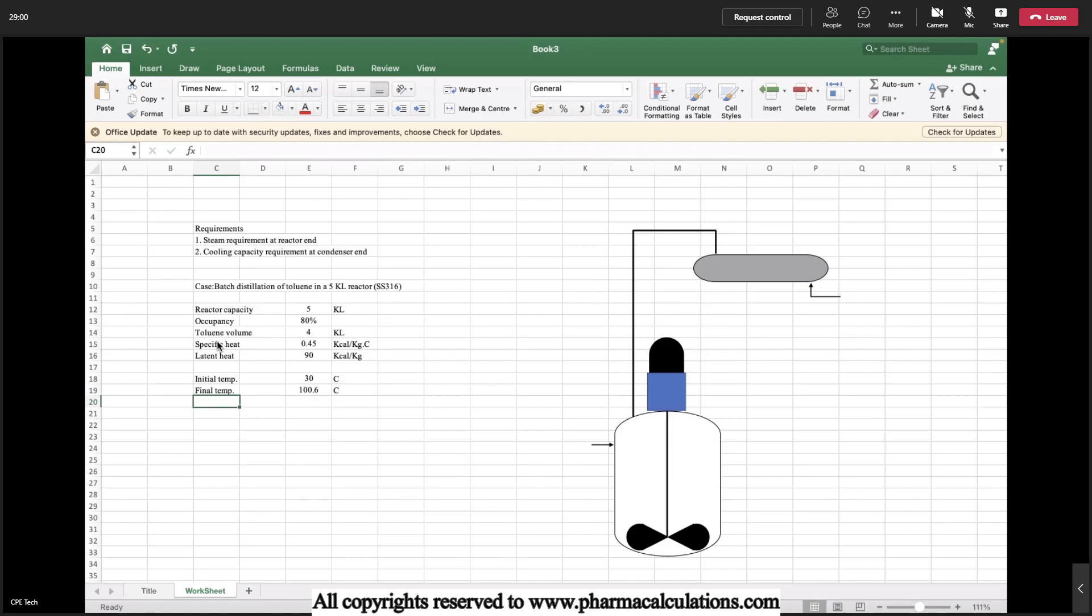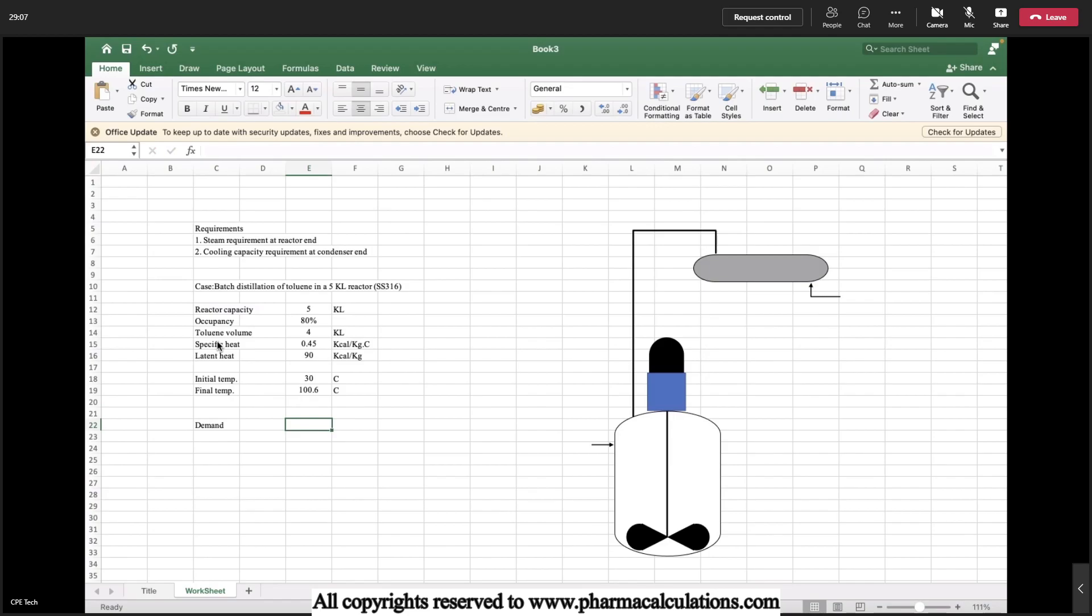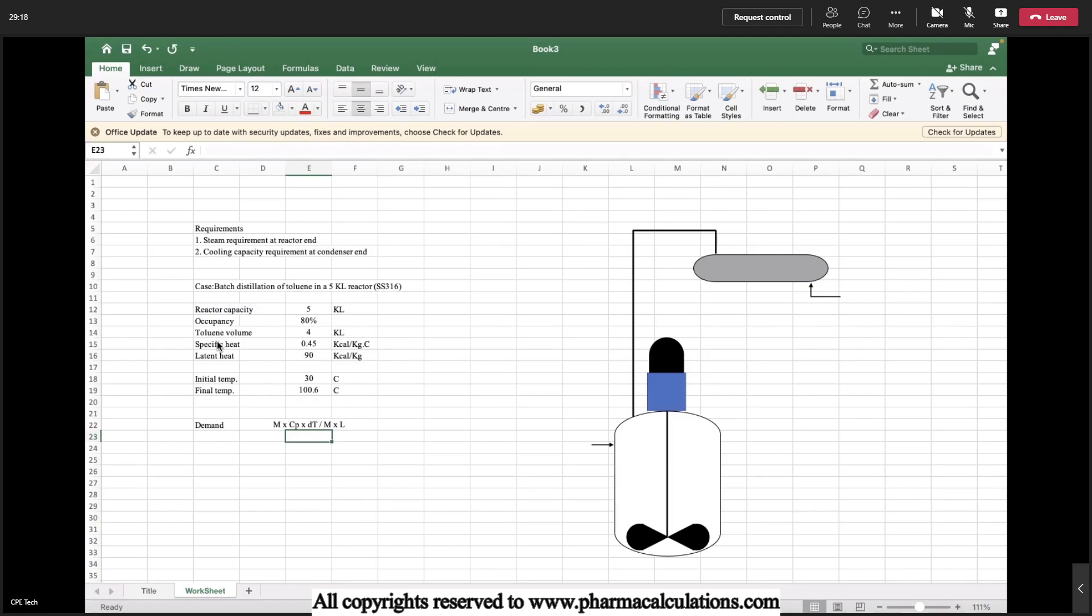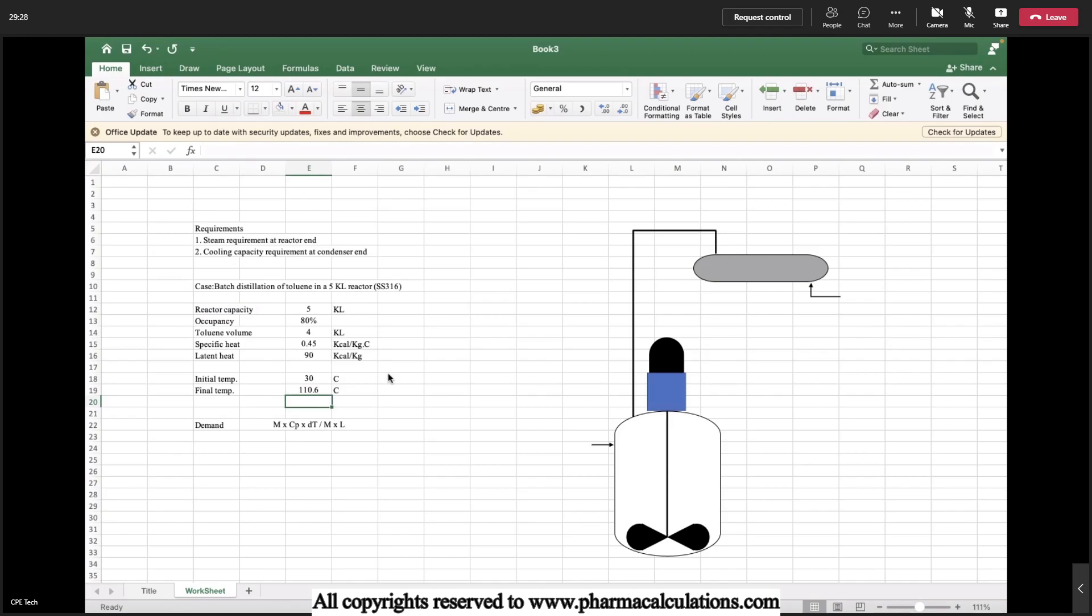Now we need to estimate the heat demand from the system. Demand shall be calculated using the formulas M CP delta T or M lambda, or sometimes with a combination of both. Here in this case, toluene is at 30 degree centigrade. So in order to heat the toluene up to its boiling point, we need to use sensible heat followed by latent heat for its evaporation.